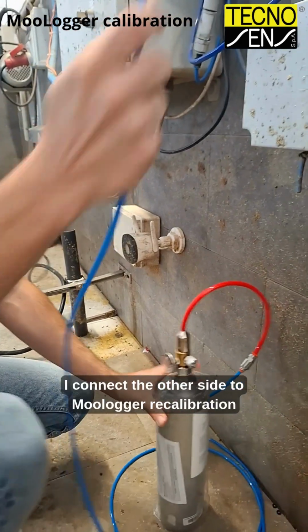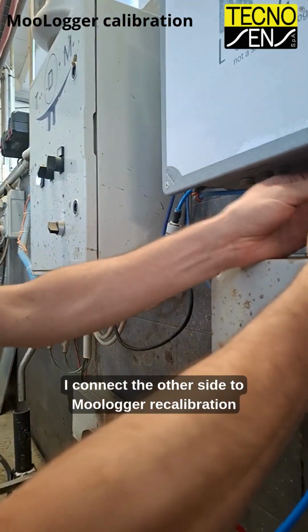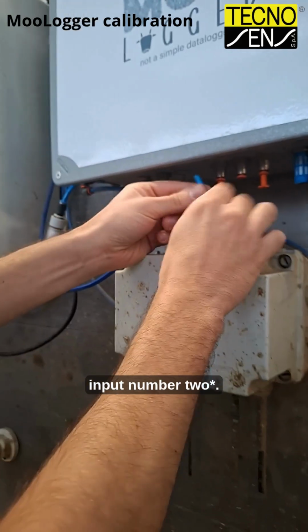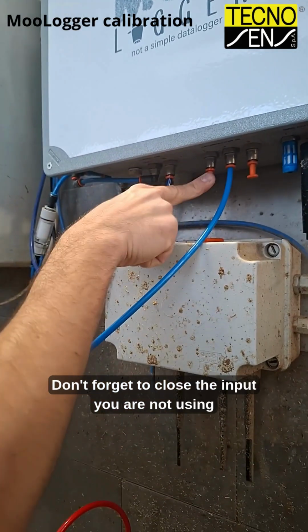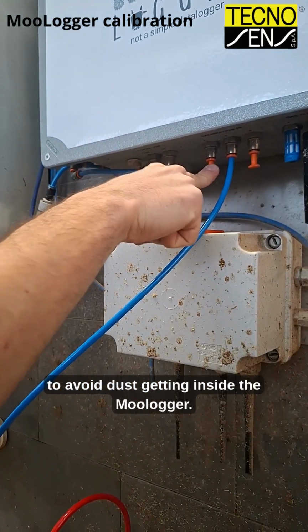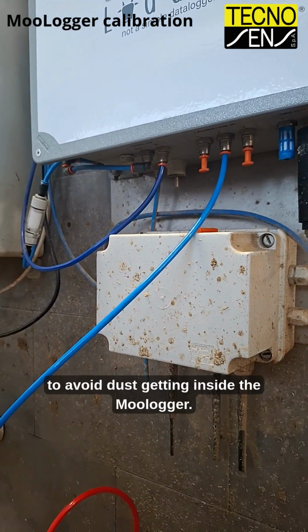I connect the other side to MooLogger recalibration input number 1. Don't forget to close the input you are not using to avoid dust getting inside the MooLogger.